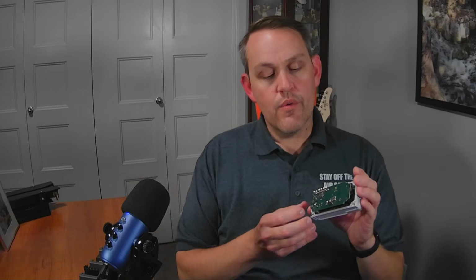It's self-diagnosing, and it goes back to the controller and says, I have an I/O fault, and gives me the exact port that it faulted on. It might be card number 6, slot 1. And it says that I/O faulted for some reason. The I/O cards are addressed. They've got little diagnostics on the back where you typically can flip some dip switches, little tiny switches on the back side, and you address the card.